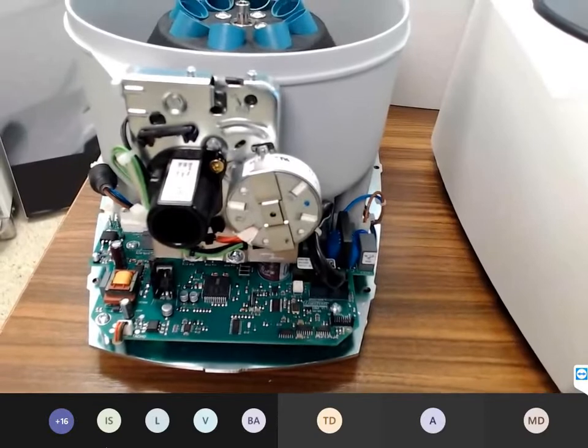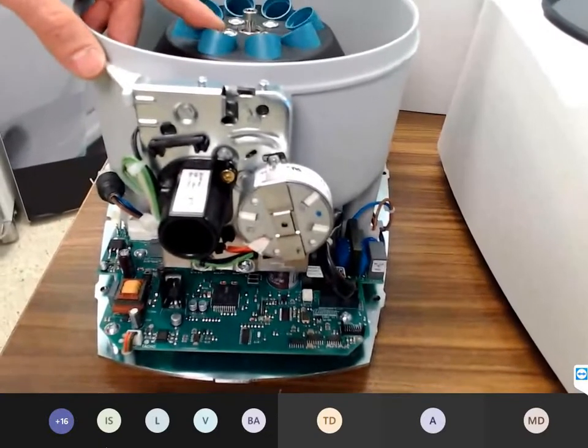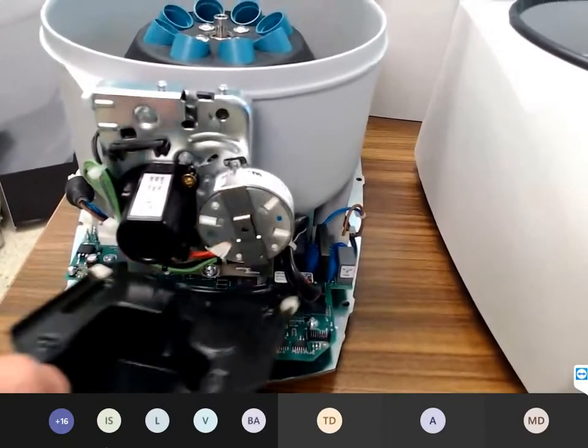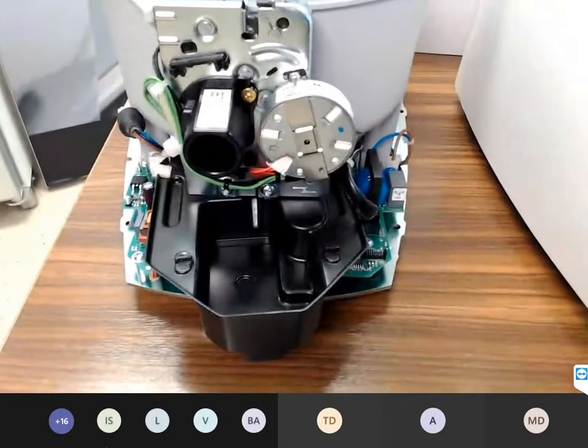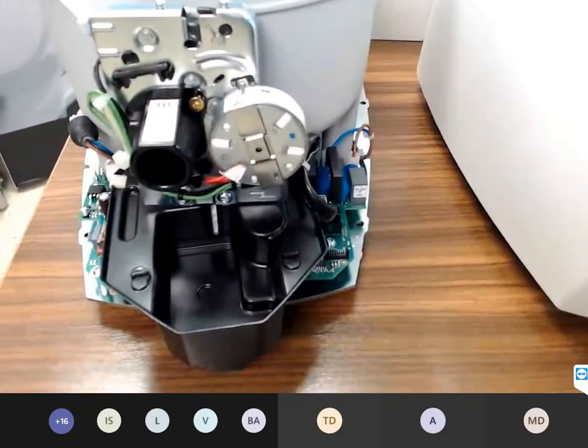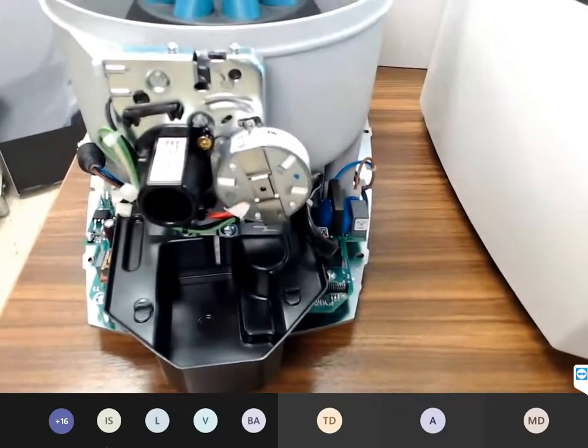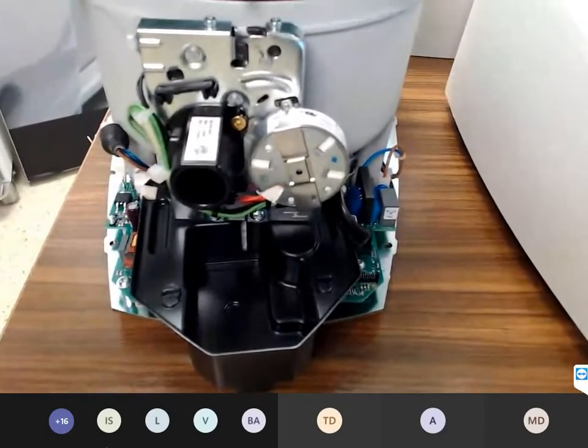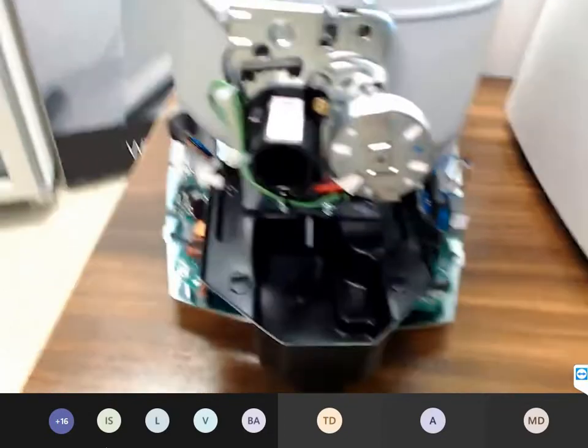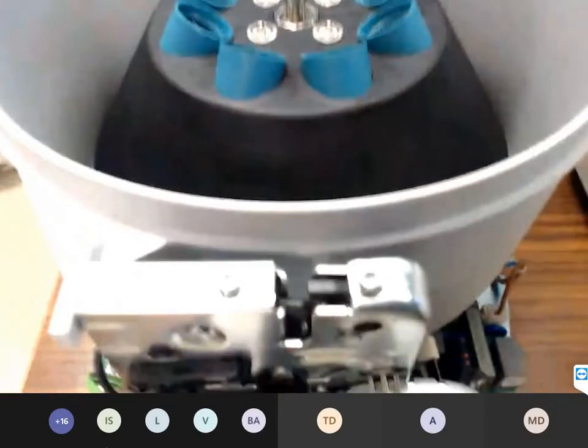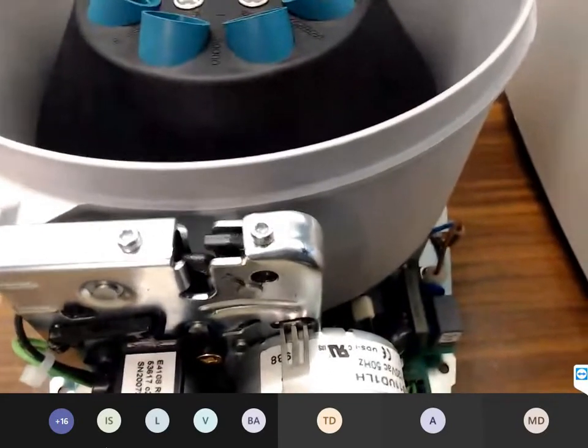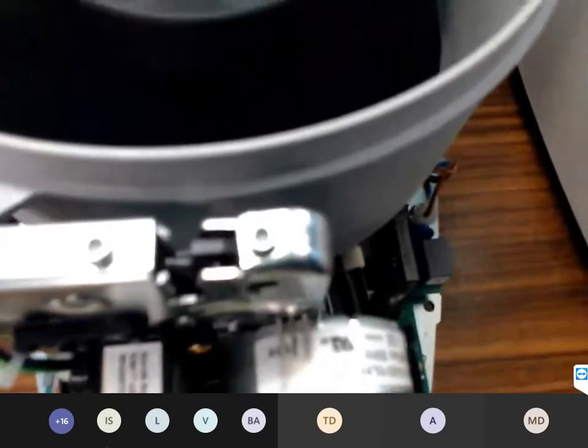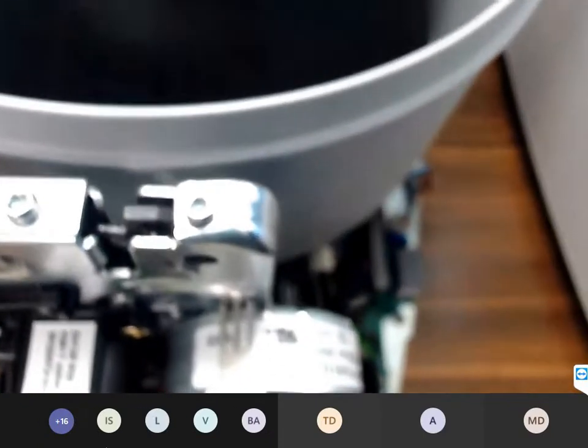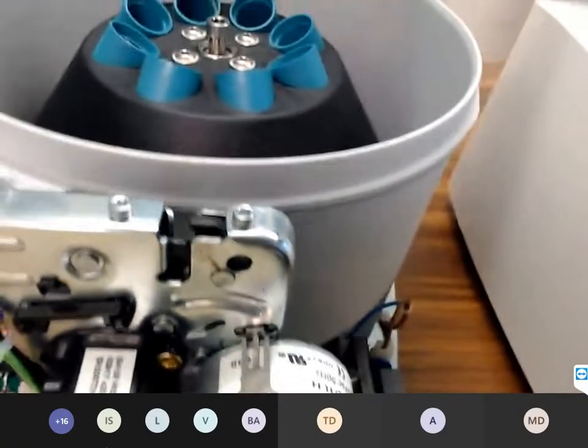We can only say, please don't fill the tubes completely or don't clean with liquid disinfection. Please clean the centrifuge with a paper towel, for example, because we have customers who go with a liquid spray, for example, and clean the centrifuge, and the liquid can flow from here onto the electronics. I think it's clear what the liquid does to the electronics. It makes a short circuit.